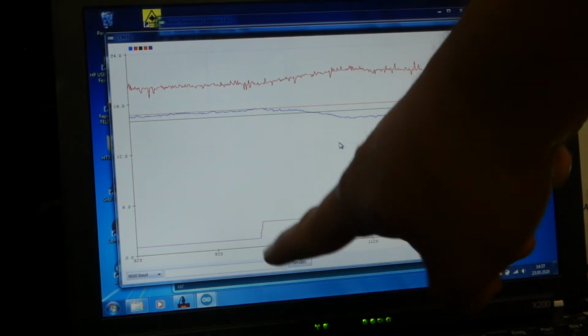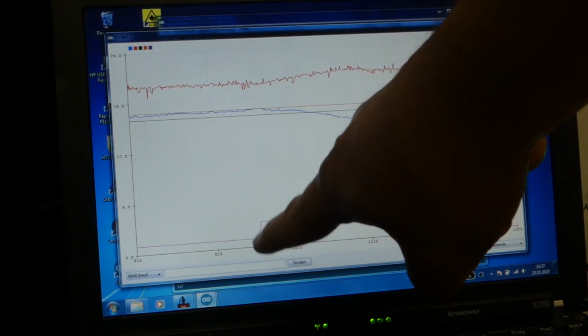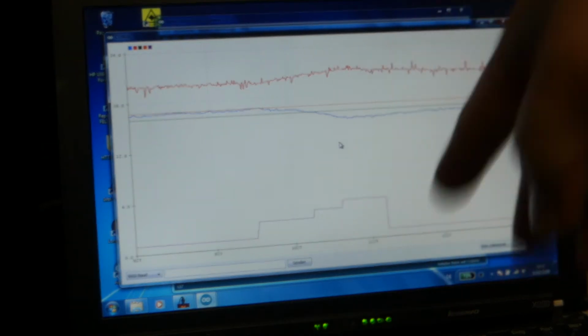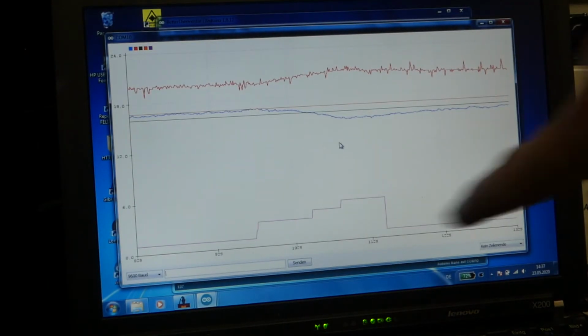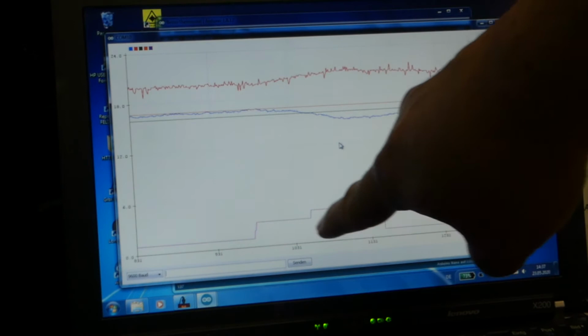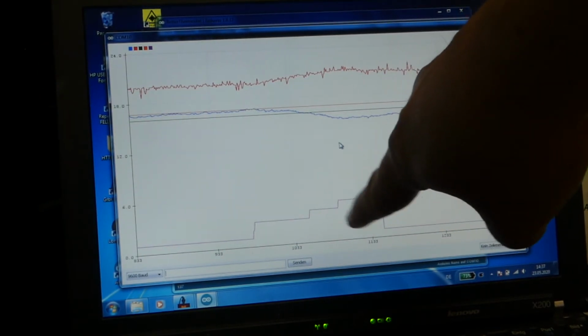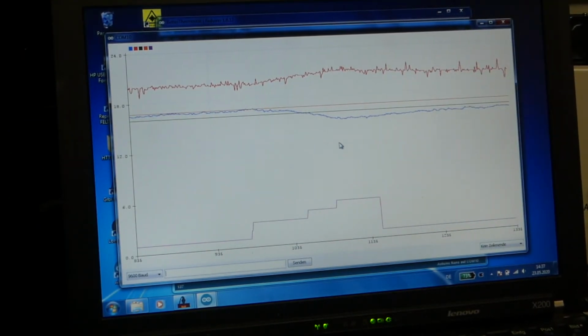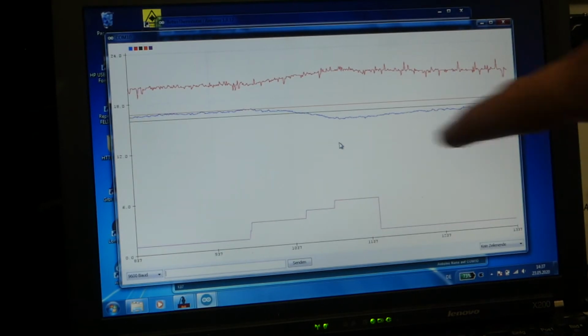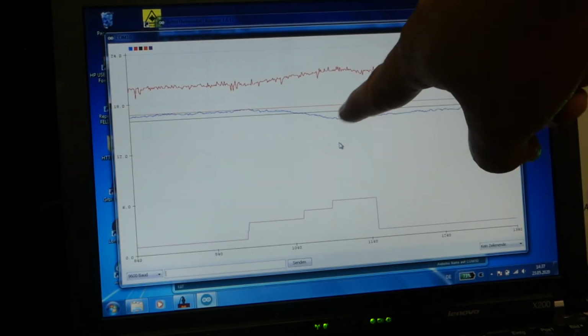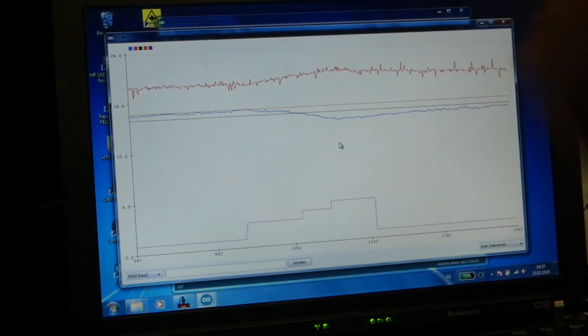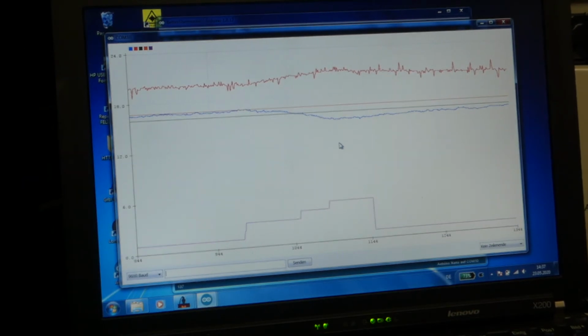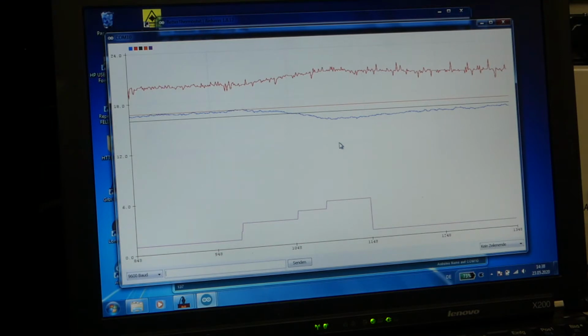So stage 1 is idle, stage 2 is very short because it's just the motor startup. Cooling held for quite some time. Then it held with the solenoid open until it had coasted to the hysteresis point, and then it went into the cool down cycle where it's just running the fan. So this is pretty much exactly what I want to have.